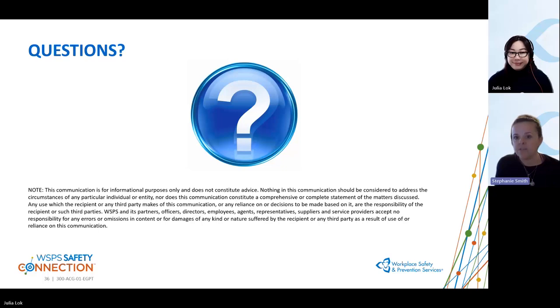If you're going in under zero energy, having placards is the best way to do it. If you're using an interlock, you need to look at that risk assessment process and determine the tasks allowed under that, making sure you're hitting most of the criteria. The CSA standard Z460 spells out what criteria you've got to hit.